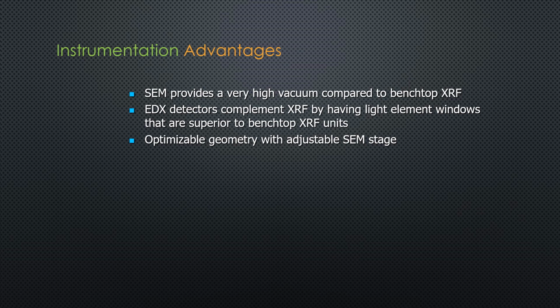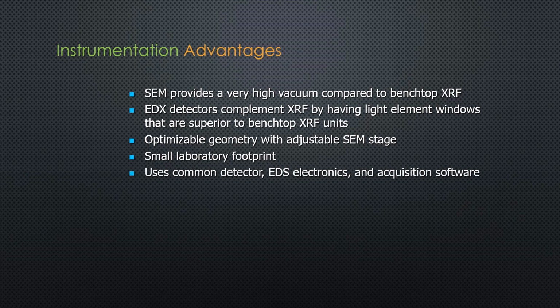With floor space cost being at a premium, adding an X-ray tube to an electron microscope creates no additional floor space or footprint. Micro XRF on the SEM uses your existing detector, your existing EDS electronics, and your existing acquisition software to acquire the Micro XRF spectrum. A Micro XRF source addition to your electron microscope is less expensive than a separate Micro XRF unit, nearly half the cost of a second XRF unit.